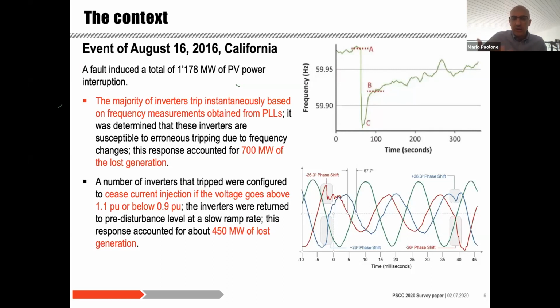There was also another issue related to some other converters that were tripping due to voltage variations beyond a window of 0.1 per unit around the nominal value. And these inverters, which were reducing their output, were coming back to the pre-disturbance power injection at a very slow ramp rate. This was essentially responsible for more than 400 megawatt of lost generation after the fault.